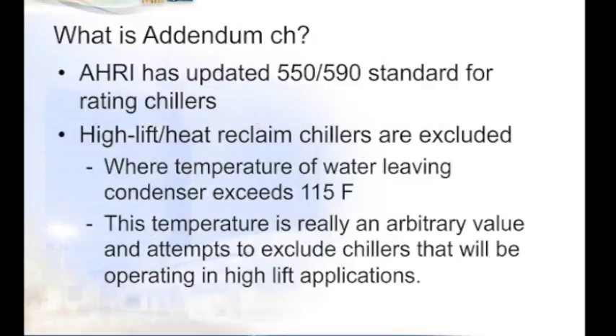And continuing with the detail of Addendum CH, another one of the changes in this soon-to-be-adopted addendum relates to the AHRI standards 550 and 590. These standards have been updated to align with the new efficiency and compliance requirements. The reference standards have also been updated to separate the standards between metric units when testing air-cooled or water-cooled chillers. Pat will also dive into more detail on the AHRI standard updates. And then finally, the addendum excludes high lift and heat reclaim chillers from compliance with 90.1.